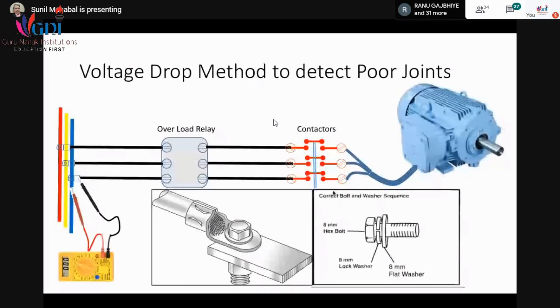I first removed this lug, and then what I found was that if this is an aluminum lug tightened on a copper bus bar, then the washer which is used ultimately comes into contact with the aluminum as well as the brass or copper.